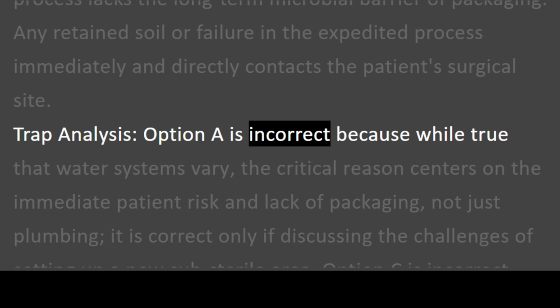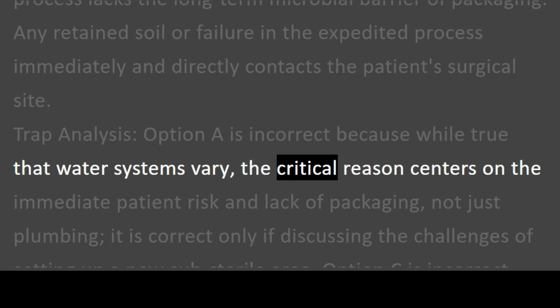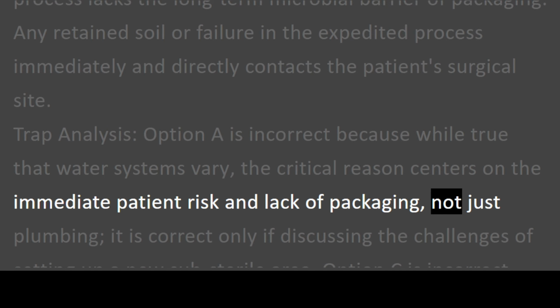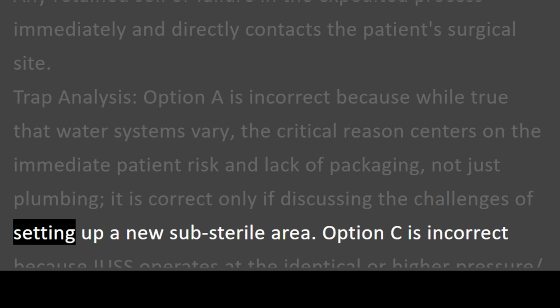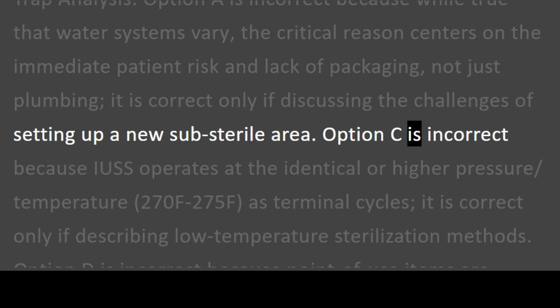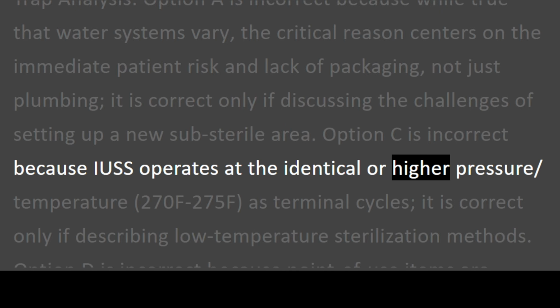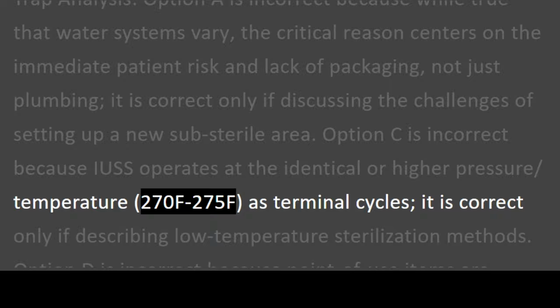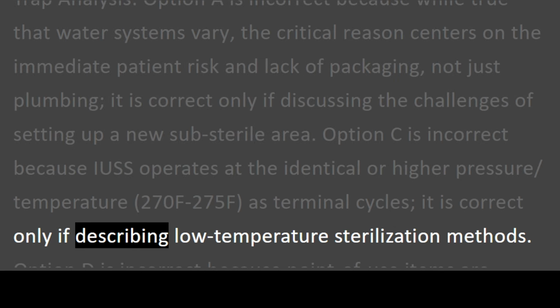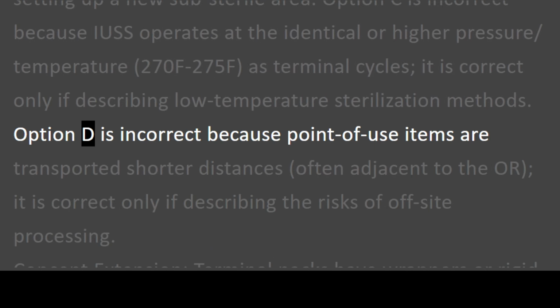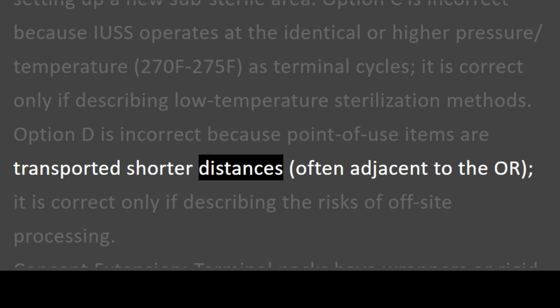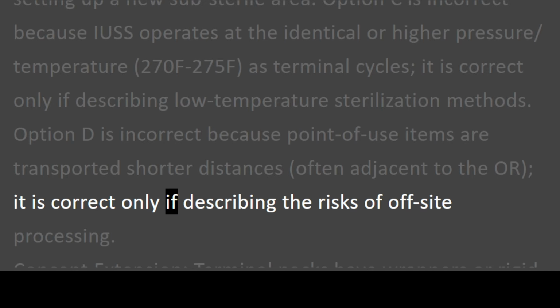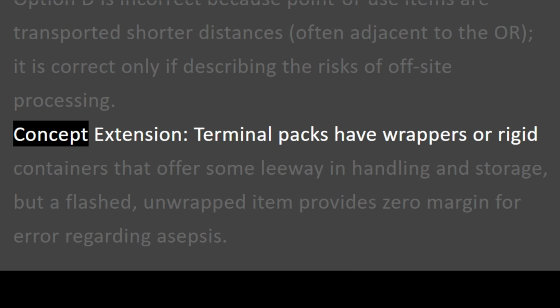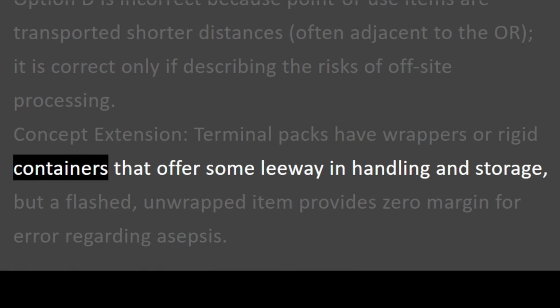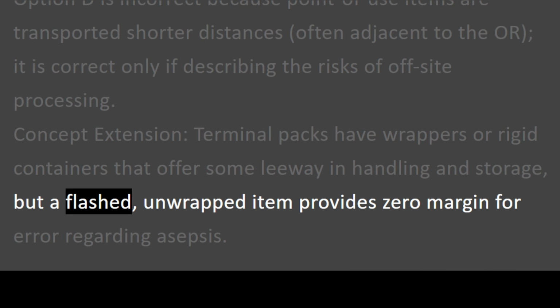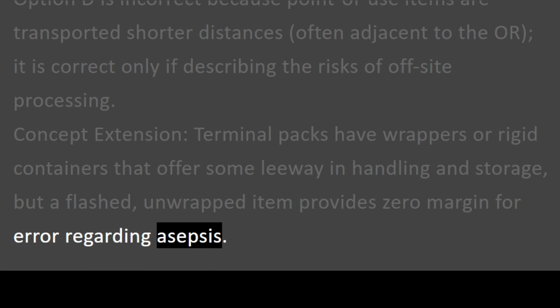Trap analysis: option A is incorrect because while it is true that water systems vary, the critical reason centers on the immediate patient risk and lack of packaging, not just plumbing. It is correct only if discussing the challenges of setting up a new sub-sterile area. Option C is incorrect because IUSS operates at the identical or higher pressure and temperature, 270 to 275 degrees Fahrenheit, as terminal cycles. It is correct only if describing low-temperature sterilization methods. Option D is incorrect because point-of-use items are transported shorter distances, often adjacent to the OR. It is correct only if describing the risks of off-site processing. Concept extension: terminal packs have wrappers or rigid containers that offer some leeway in handling and storage, but a flashed, unwrapped item provides zero margin for error regarding asepsis.